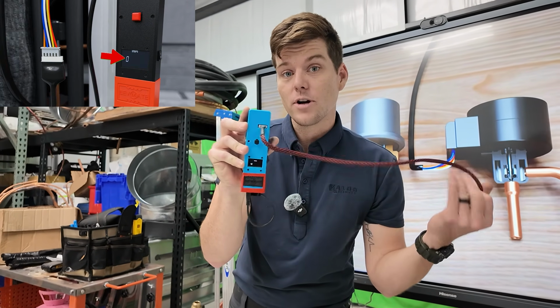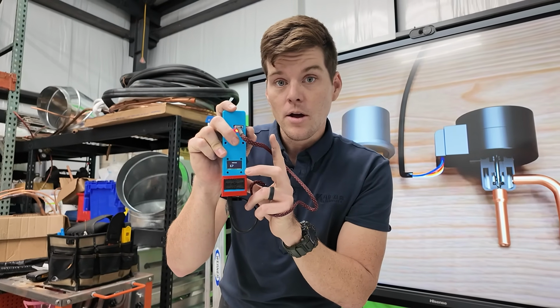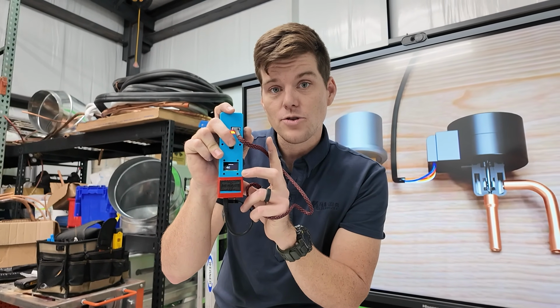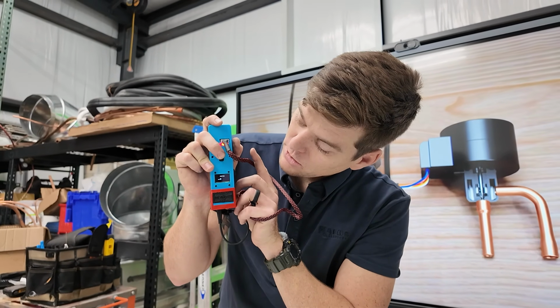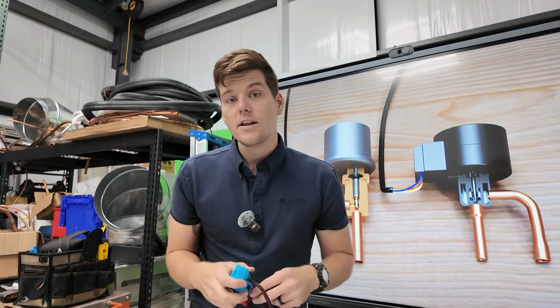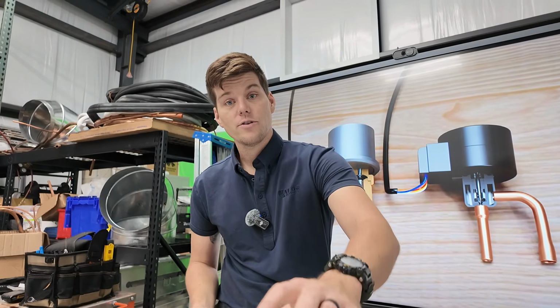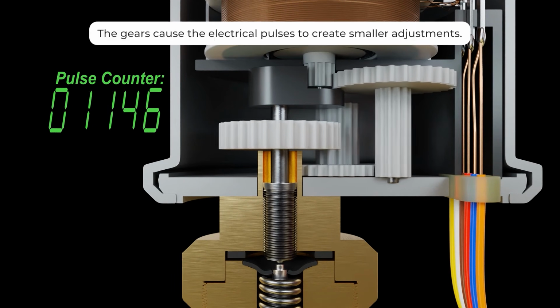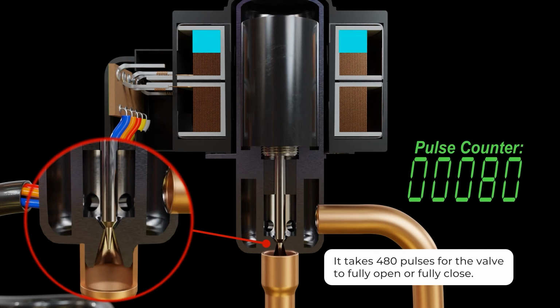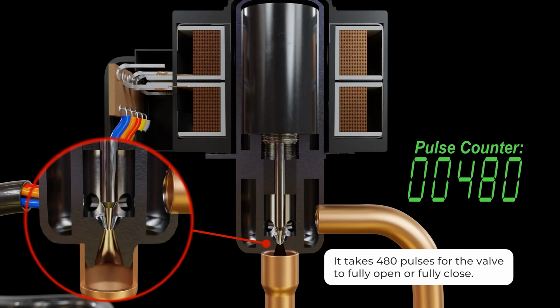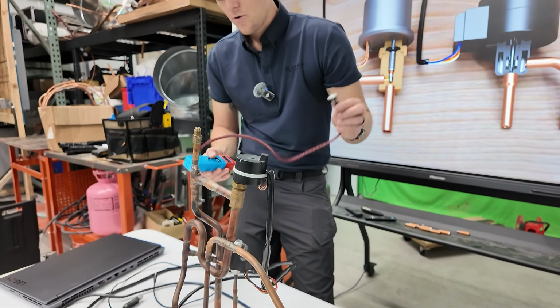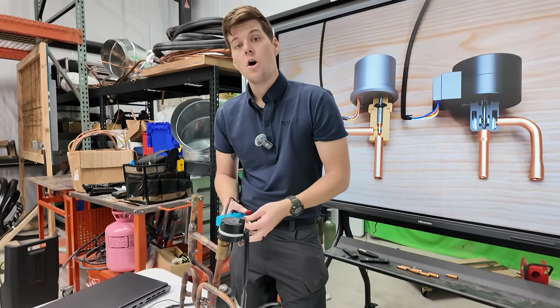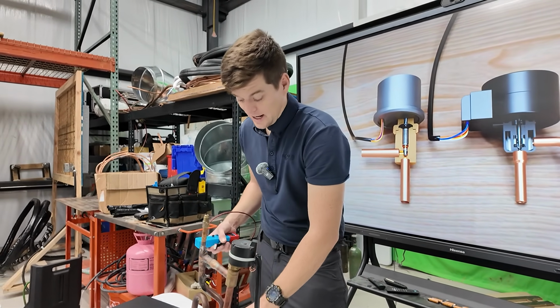This is important because if we're going to manually drive this, I can drive it up, which is positive pulses, or drive it down, which once we get past 0 goes into negative pulses. Understanding the type of electronic expansion valve you have, whether it's a 0 to 2000 or a 0 to 480 with this indirect drive, is important. You don't want to overdrive the valve too much, although you can in some troubleshooting scenarios.